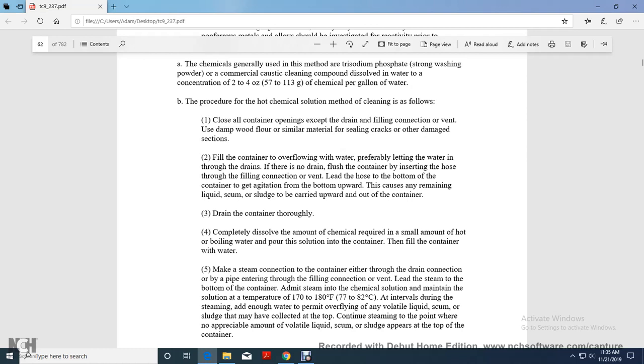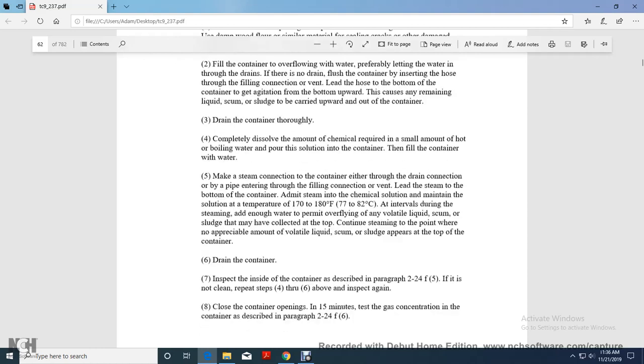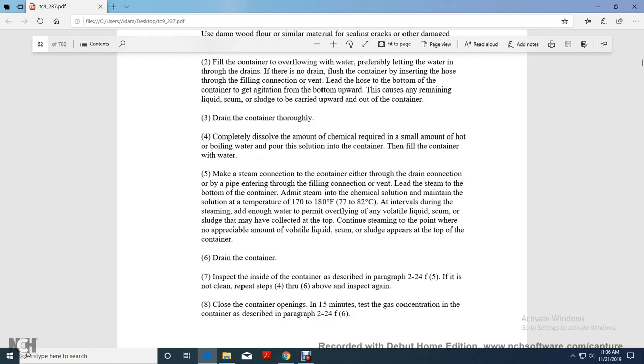Fill the container until the water overflows, preferably letting the water in through the drain. If there is no drain, flush the container by inserting a hose through the filling connection or vent. Lead the hose to the bottom of the container so that the agitation goes from the bottom upward. The scum of the remaining liquid and the sludge are carried upward out of the container. Drain the container thoroughly. Completely dissolve the required amount of the chemical in a small amount of hot or boiling water. Pour the solution into the container. Fill the container with water.